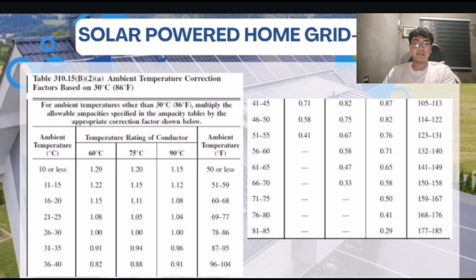So, how do you use it? Find your temperature. Look at the far left or far right columns to find the expected ambient temperature of your installation. Select your conductor rating. Choose the column that matches your wire insulation rating, usually 75 Celsius or 90 Celsius for modern solar wiring like THWN-2 or PV wire. The number where they meet is your correction factor.